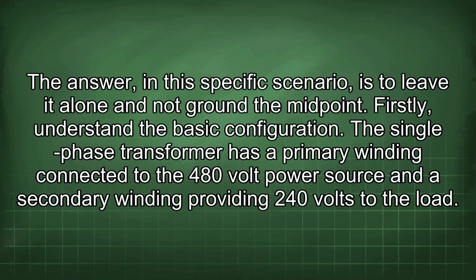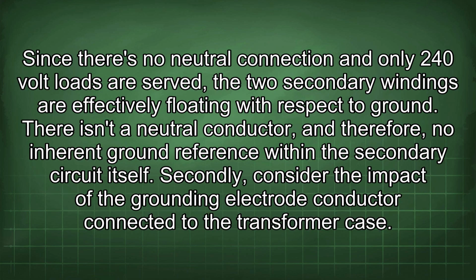Firstly, understand the basic configuration. The single-phase transformer has a primary winding connected to the 480 volt power source and a secondary winding providing 240 volts to the load. Since there's no neutral connection and only 240 volt loads are served, the two secondary windings are effectively floating with respect to ground. There isn't a neutral conductor, and therefore, no inherent ground reference within the secondary circuit itself.